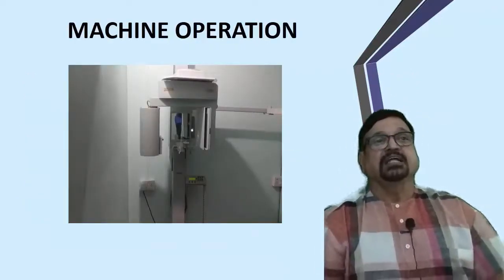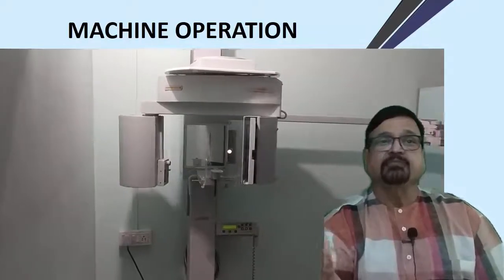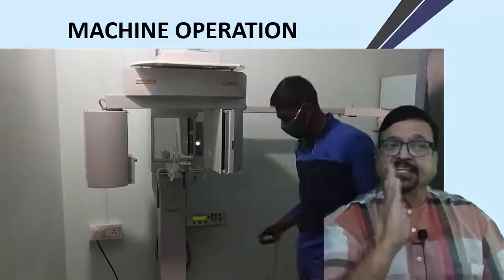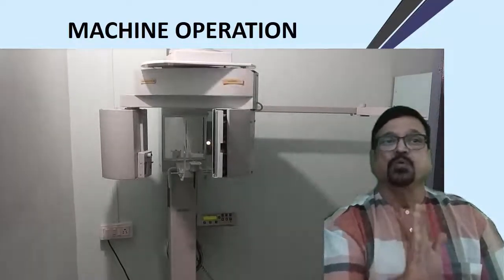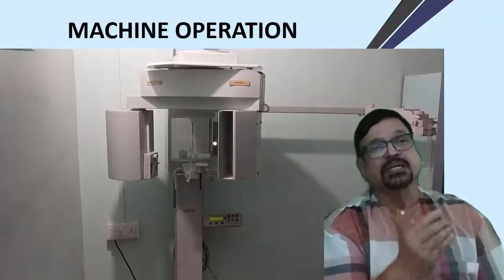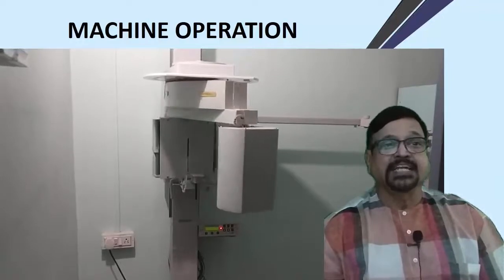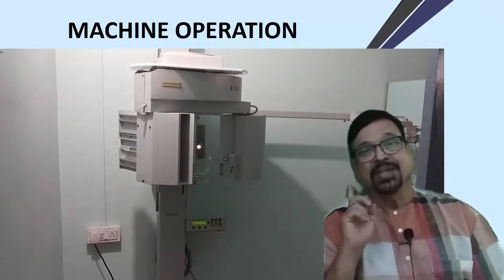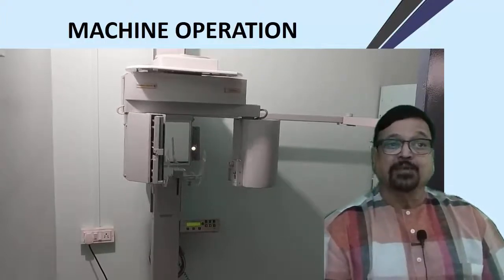Now this is the machine - you can see how it is operated. From where the radiation starts, the machine takes a little before-position so that when the arc starts moving it will reach its optimum speed. The technician inserts a cassette and fixes it so it will not move. The left side is the tube and the right side is the cassette. When the machine moves, the cassette also moves from one end to the other. You can see while rotation is going on, the cassette is also moving and the tube is also moving, while the patient in the center remains steady.